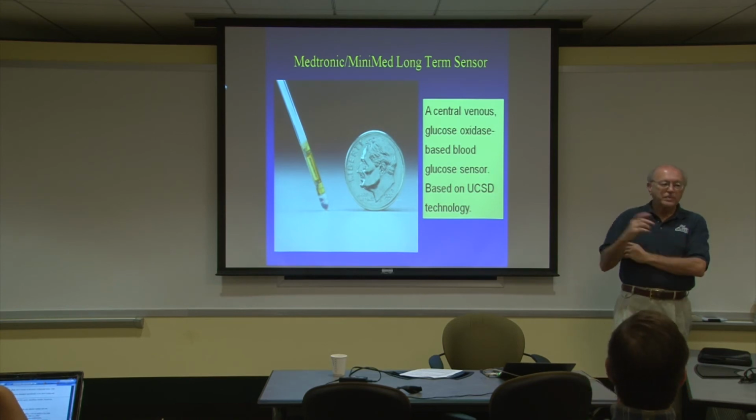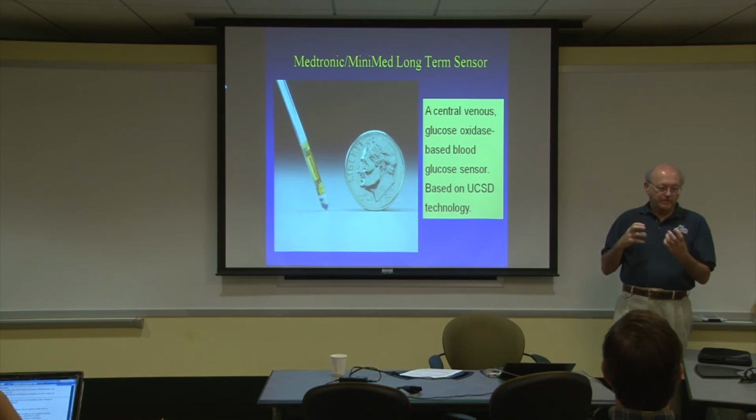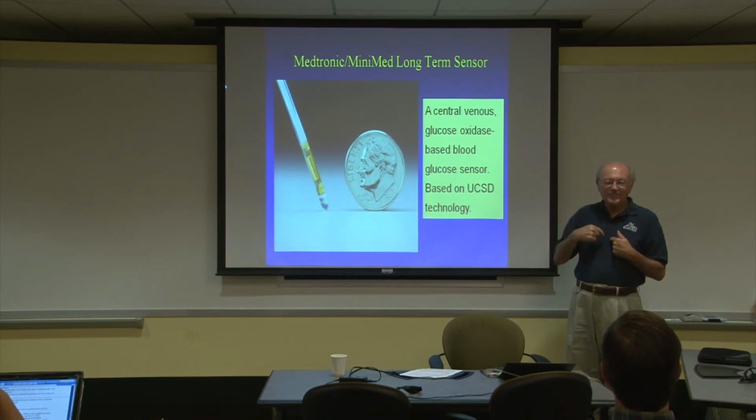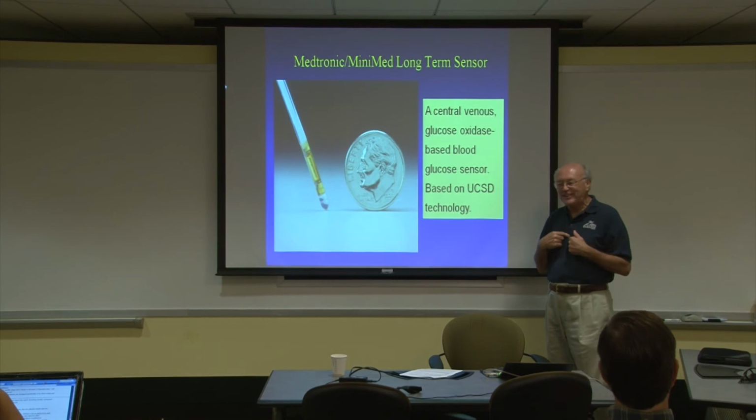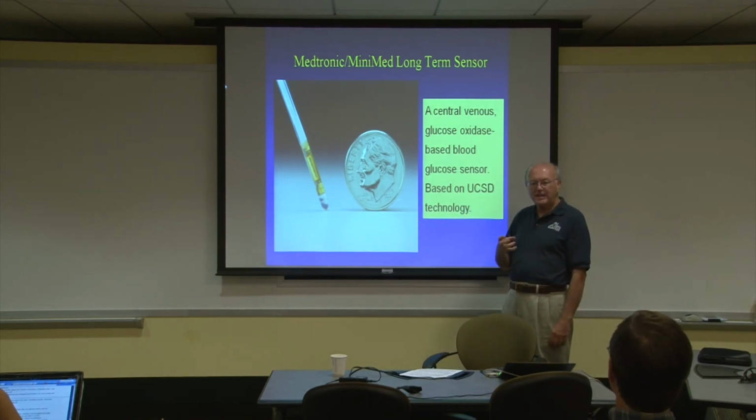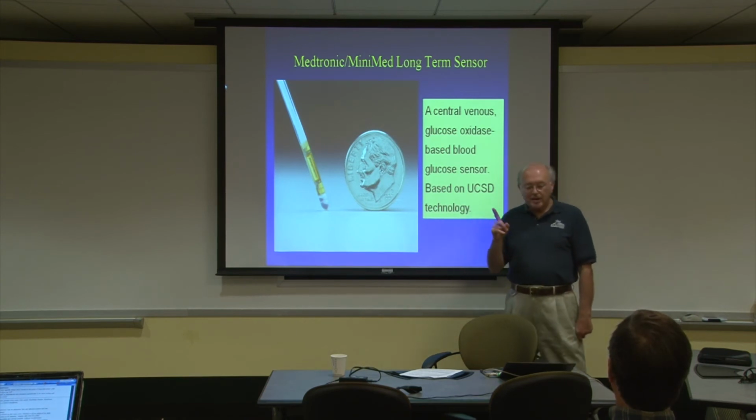The important message is if you put this thing anywhere on the arterial side, it's going to thrombose, no matter what. Within a matter of minutes even. Okay, well, let's use anticoagulants. No, we're not going to use anticoagulants for a lifetime just to operate this device. Right. And so the arterial side's out. On the arterial side, blood goes to your brain or to your heart, so if you make a clot, you've got a big problem. But on the venous side, it's all different. So that's an important message.